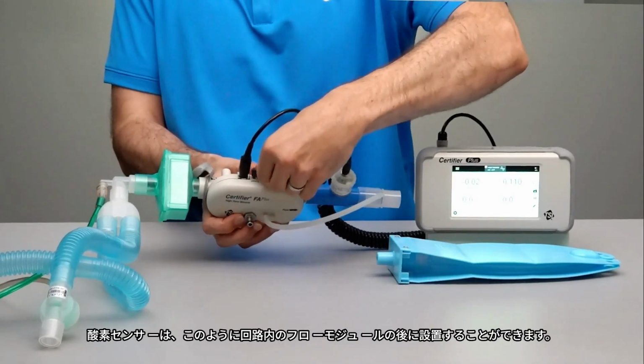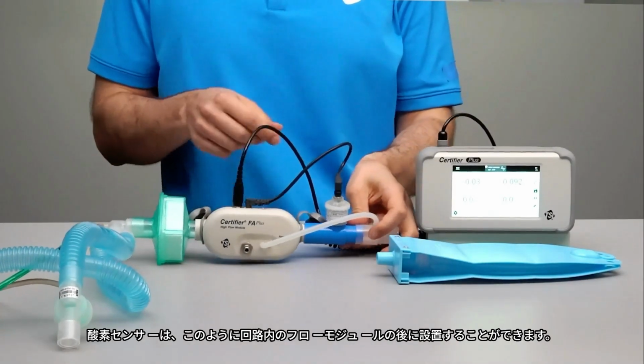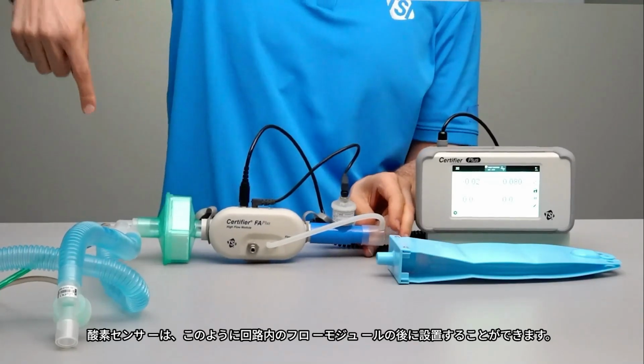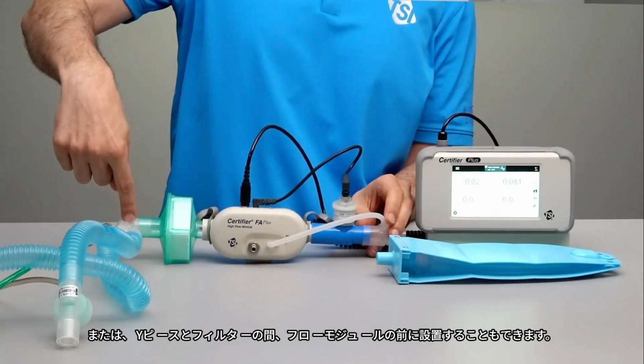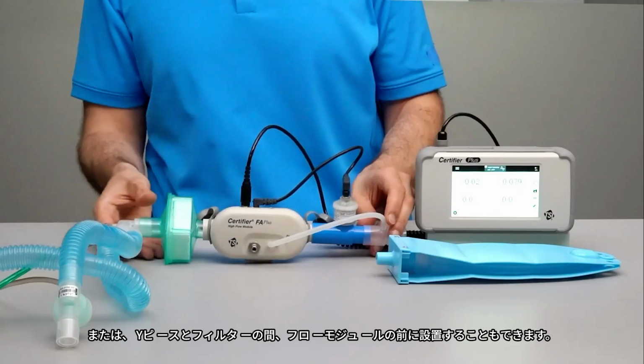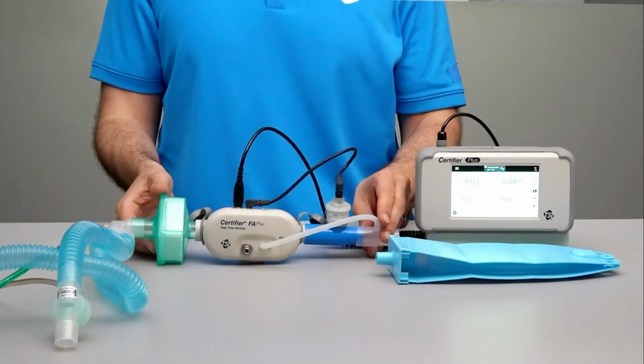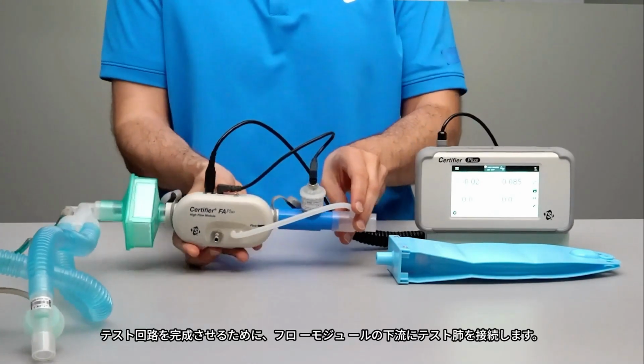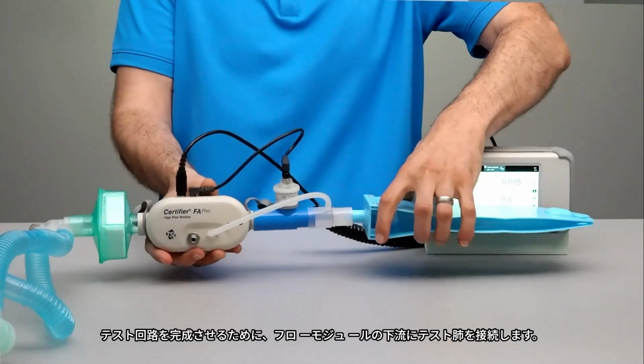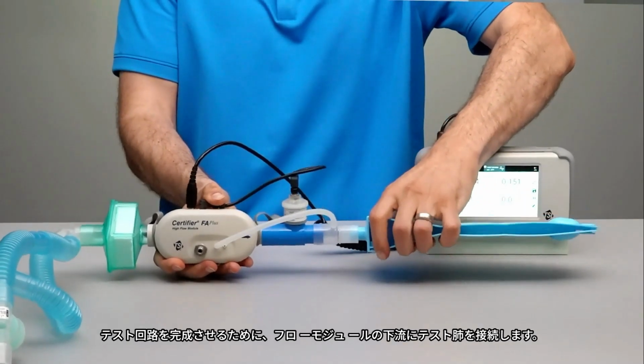The oxygen sensor could be installed in the circuit after the flow module, as shown here, or it could be installed before the flow module between the Y fitting and the filter. To complete the test circuit, we will connect the test lung downstream of the flow module.